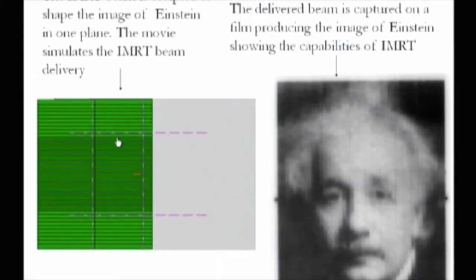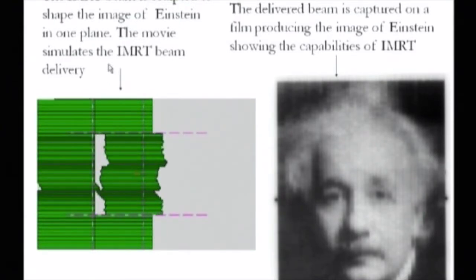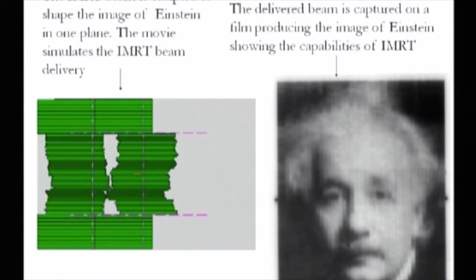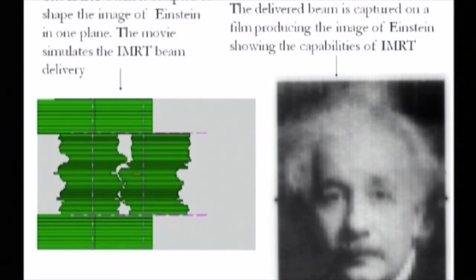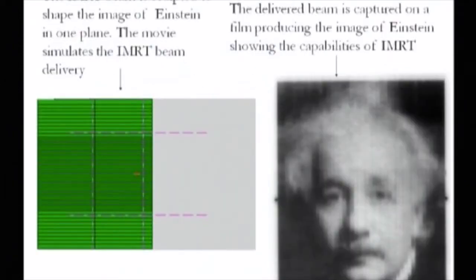So if I could run the video on the left-hand side, here is a typical movement of the lead fingers from the left side to the right side. And on the right side, this is an image that is developed on a film. As you can see, by controlling the speed of the collimators, we can sculpt out different images, as demonstrated here. The white portion obviously has more photons. The black portion has fewer photons delivered to it. So by time modulating the X-ray delivered, we can actually change the amount of photons tissue receives. In the resolution we're looking at, it's about 2 millimeters. So you're looking at 2 millimeters in width for the lead fingers.